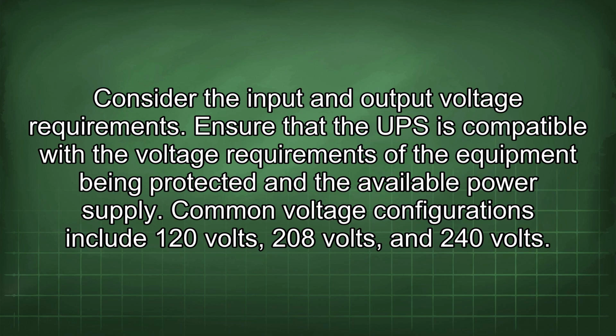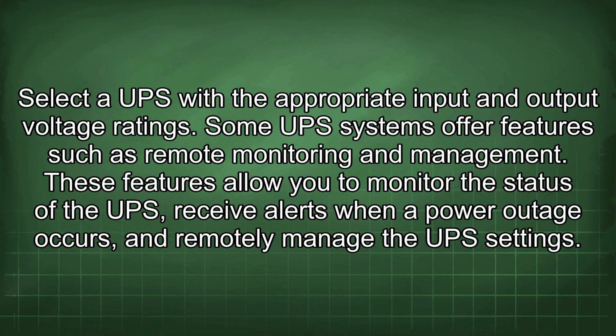Consider the input and output voltage requirements. Ensure that the UPS is compatible with the voltage requirements of the equipment being protected and the available power supply. Common voltage configurations include 120 volts, 208 volts, and 240 volts. Select a UPS with the appropriate input and output voltage ratings.